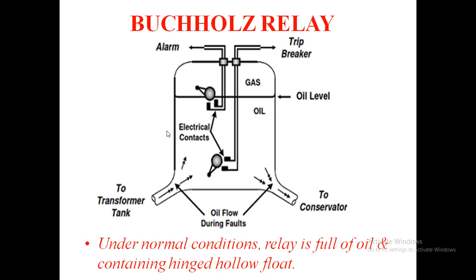So this is our circuit diagram representation, the basic arrangement of this relay. Under normal condition, the relay is full of oil and contains a hinged hollow float. It consists of a cast housing containing the hinged hollow float. A mercury switch is attached to the float, the float being rotated in the upper part of the housing. The flap valve is located in the lower part, which is directly in the path of oil between tank and conservator. Another mercury switch is attached to the flap valve. The float closes the alarm circuit, while the lower valve closes the trip circuit in case of internal fault.